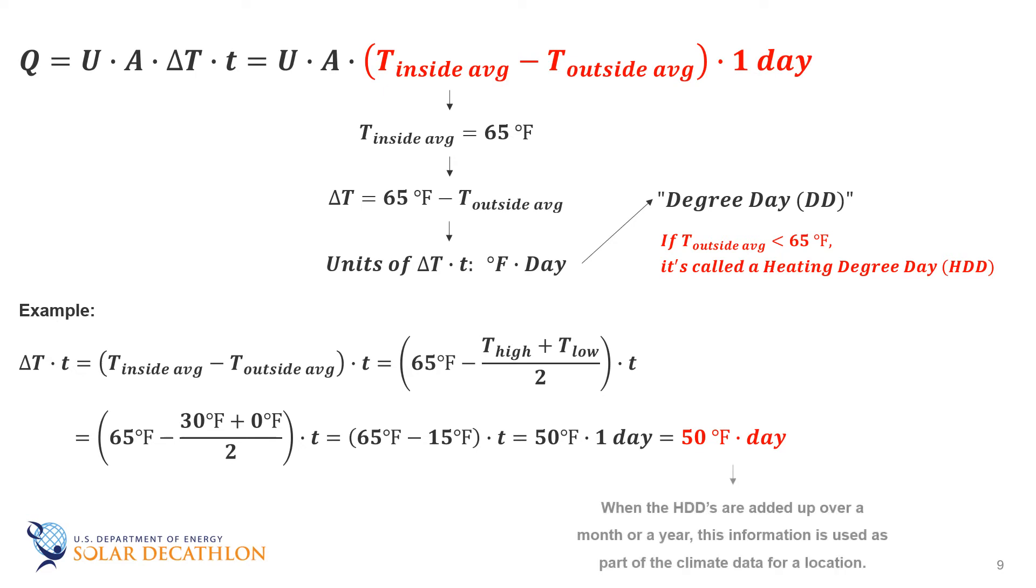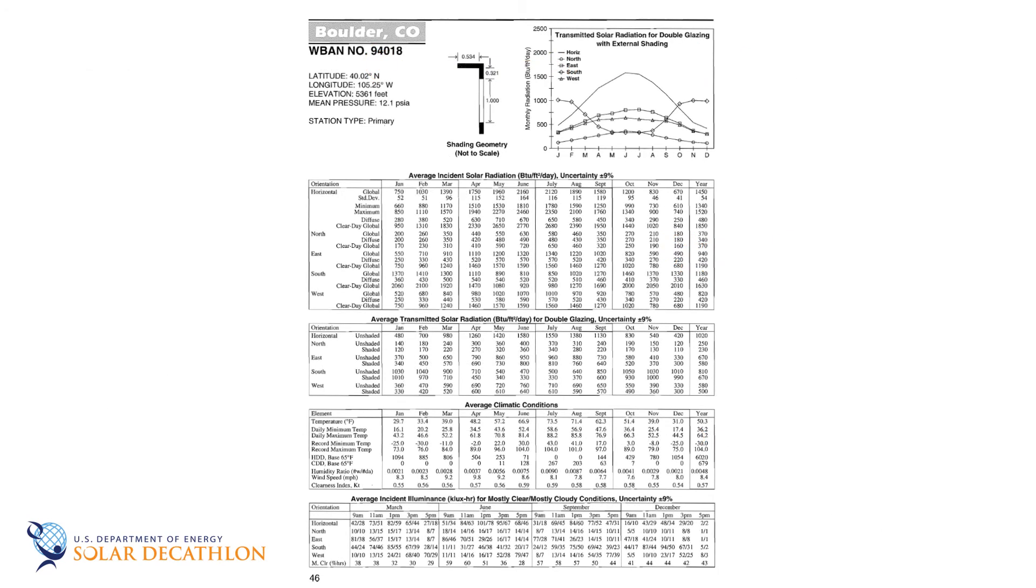We can add up degree days for a month or even a year and report that information as part of climate data. Many energy efficiency building codes use heating degree days as the basis for climate zones and for determining the minimum level of energy efficiency requirements for heating and cooling equipment. The heating degree days are tabulated in a number of places with some examples provided in the reference section. While dated, the TMY-based heating degree days are located in an NREL publication. They are tabulated by location. As you can see in this example below, the information is tabulated on a monthly basis as well as an annual basis.